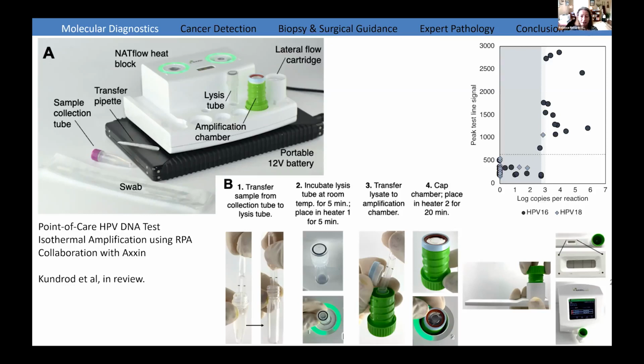And so we've evaluated this again using clinical samples that were self-collected in this case, and we compared the results to quantitative PCR. It was detecting HPV 16 and HPV 18, with samples that are both 16 or 18 positive, as well as a number of samples that were negative. On the y-axis, you see the test line signal from this assay. On the x-axis, you see the concentration of HPV DNA. And you can see above 3 log copies per reaction, we have really excellent results with the assay. We also have completely clean negatives. And so we need to push the limit of detection down a little bit to the limit of detection that is possible with PCR.